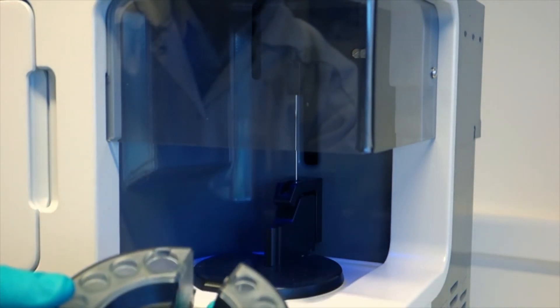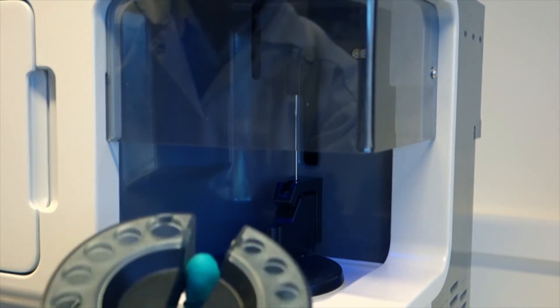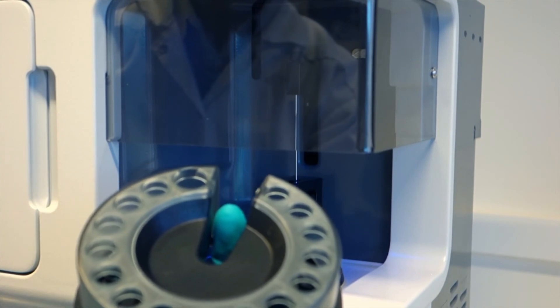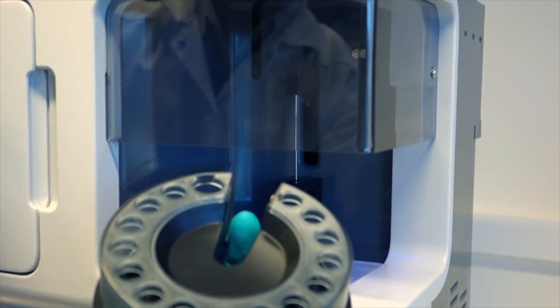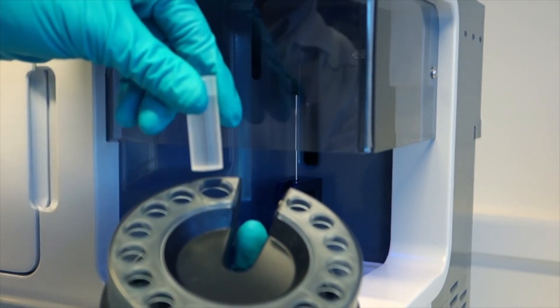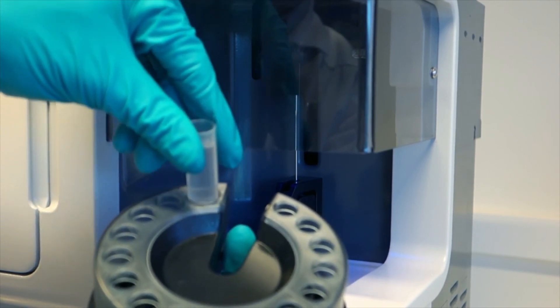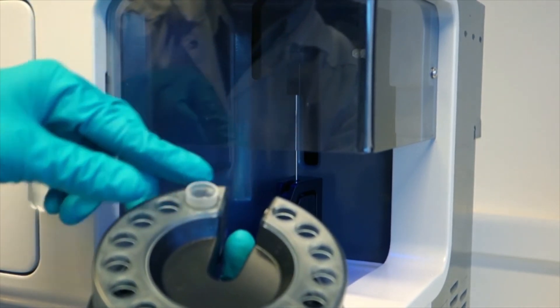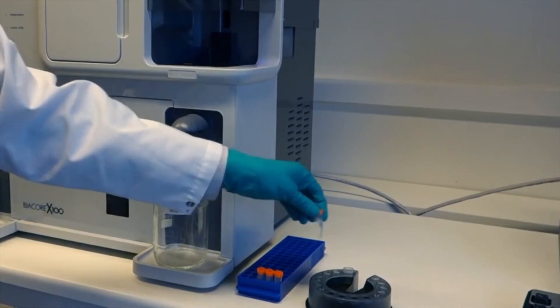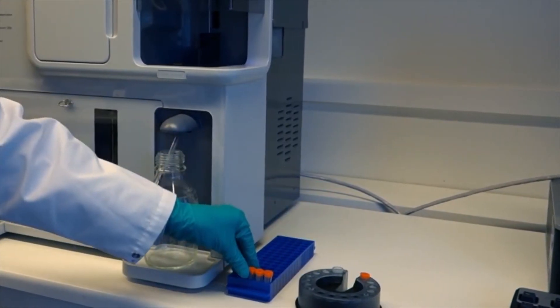Fill a 4ml vial with water. Always use fresh water filtered through a 0.22 micron filter to remove particles. Do not cap the 4ml vial. The water is used for needle cleaning during the run and during standby. Place the samples into the reagent rack.